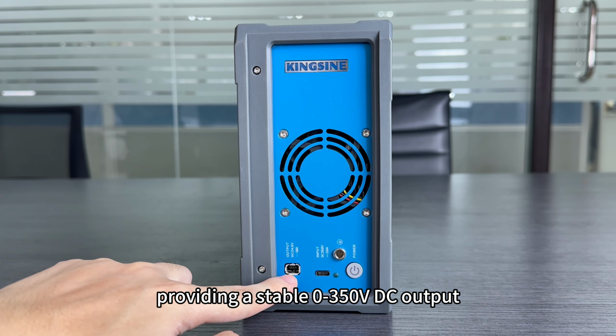The DC test module offers similar functionality to AC testing, but specifically controls DC voltage and current outputs and variables. With the state sequence feature, we can program multiple test states, perfect for measuring protection devices' action times, return time, and repeated auto-reclosure processes.